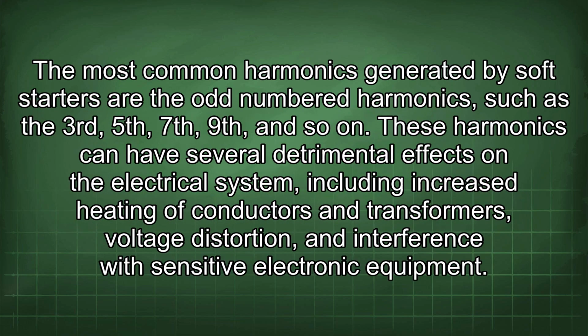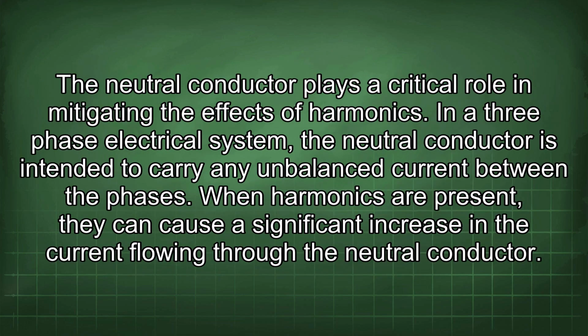The most common harmonics generated by soft starters are the odd-numbered harmonics, such as the 3rd, 5th, 7th, 9th, and so on. These harmonics can have several detrimental effects on the electrical system, including increased heating of conductors and transformers, voltage distortion, and interference with sensitive electronic equipment. The neutral conductor plays a critical role in mitigating the effects of harmonics. In a three-phase electrical system, the neutral conductor is intended to carry any imbalanced current between the phases. When harmonics are present, they can cause a significant increase in the current flowing through the neutral conductor.